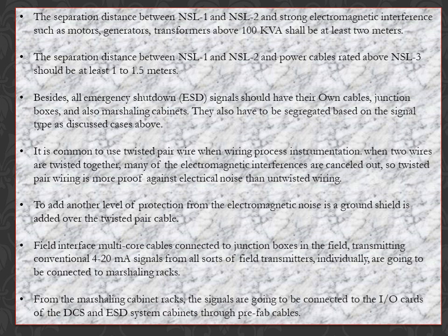Field interface multicore cables are connected to junction boxes in the field, transmitting conventional 4 to 20 mA signals from various field transmitters individually, and are connected to marshalling racks. From the marshalling cabinet racks, the signals are connected to the I/O cards of the DCS and ESD system cabinets through prefabricated cables.